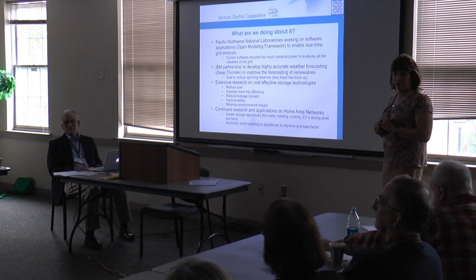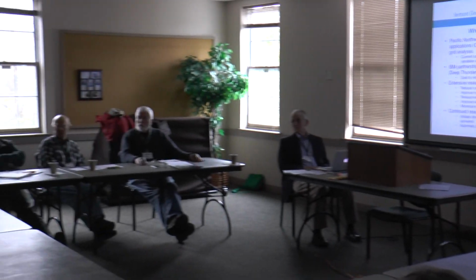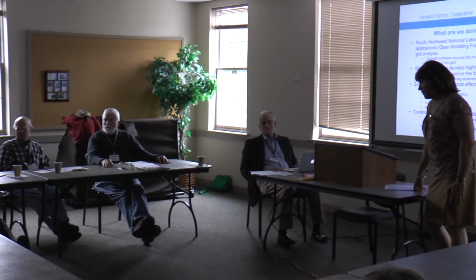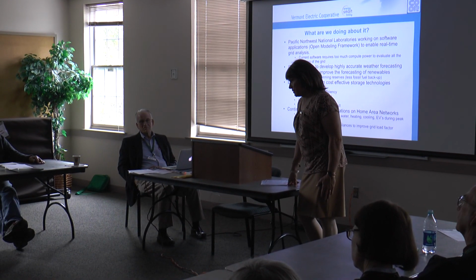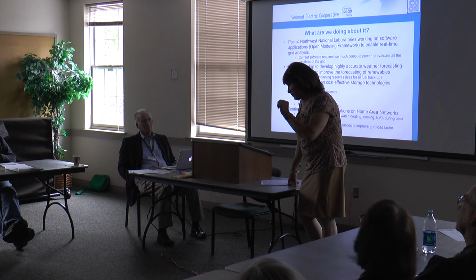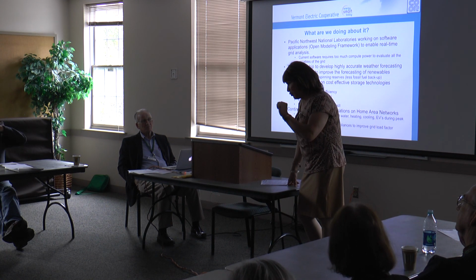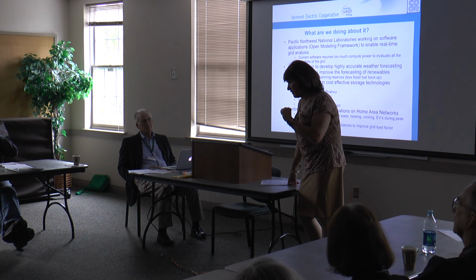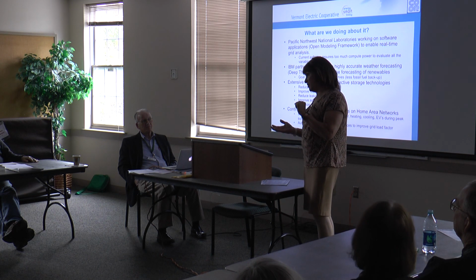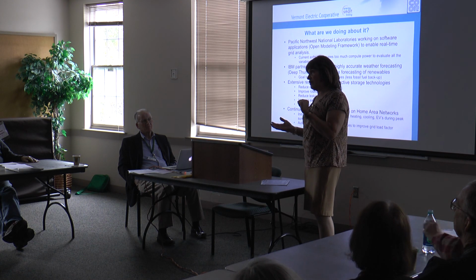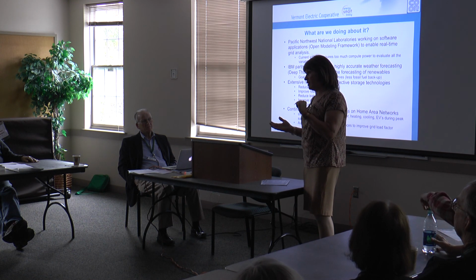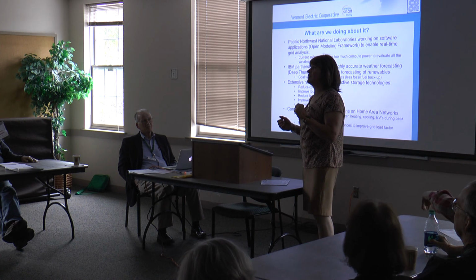Other questions? How much of a frequency drop does it take to get the thing leveled off? When you overload a little bit, your frequency drops, and then you pick up something and it gets back up. How much of a frequency loss trips that? Our set point for these field devices is 59.62 cycles, so that's when it'll drop out the lines. But the grid operators try to keep the frequency within 1%, and they have 5% limits.